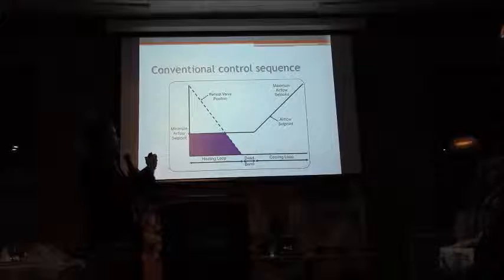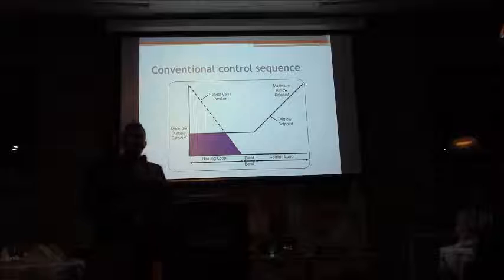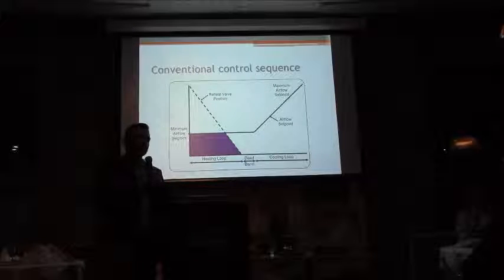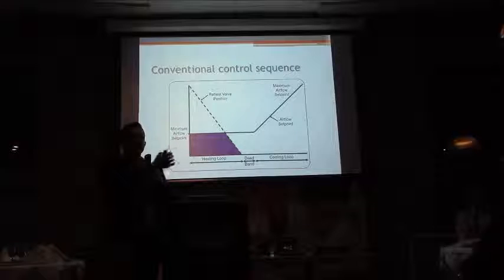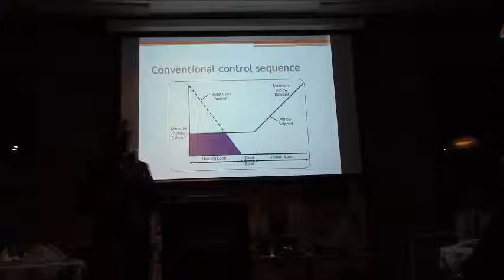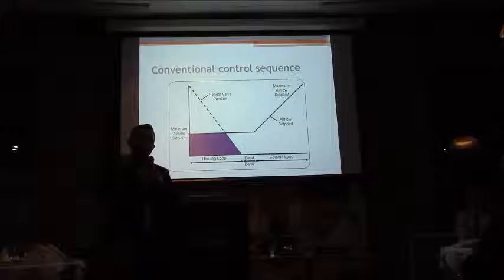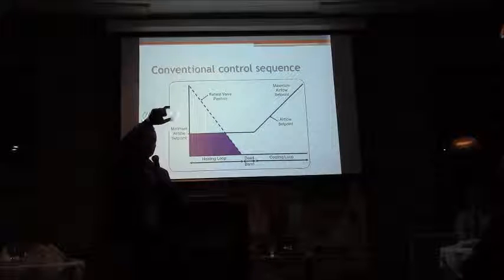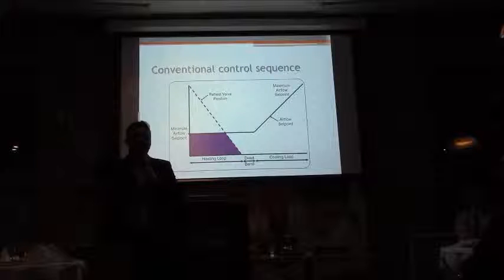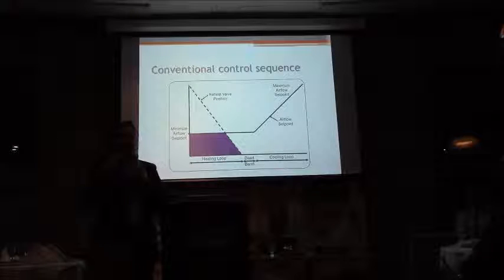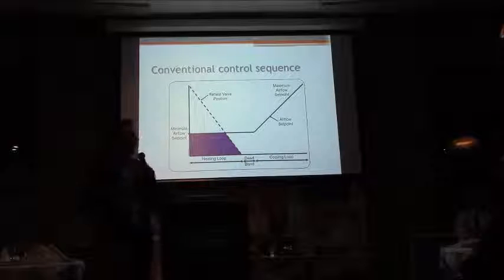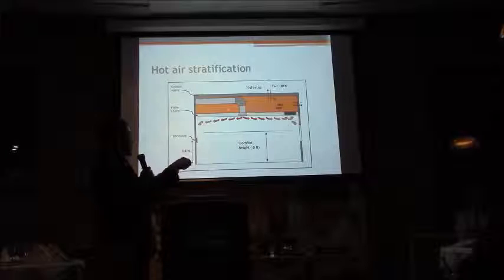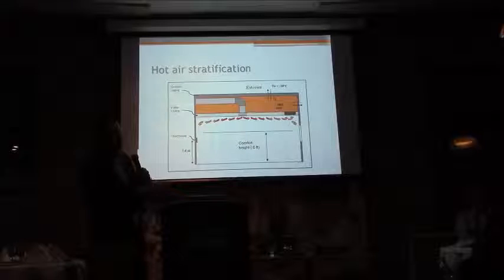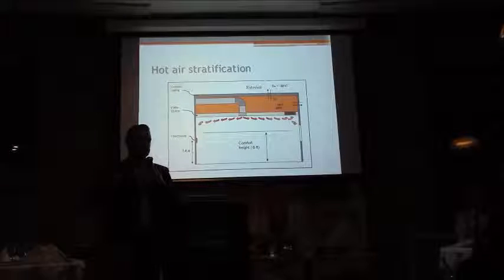And whenever I do an airflow test at our lab, we have a lab in Montreal where we could do smoke shows. Any diffuser that we have, we could test them at different CFMs, at different temperatures, and we can inject smoke into the airstream to show exactly the type of airflow that we have based on the diffuser. And the test that I enjoy doing is always the cone diffuser in heating mode. And you see the smoke just staying on the ceiling, never coming down into the occupied zone. That's heated air that we're just wasting. And what happens often is that some of that air is just bypassed to the return. So you heat that air and then you return it. That's a big waste of energy.